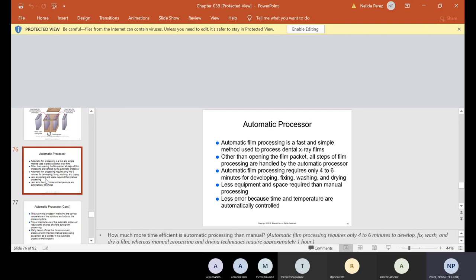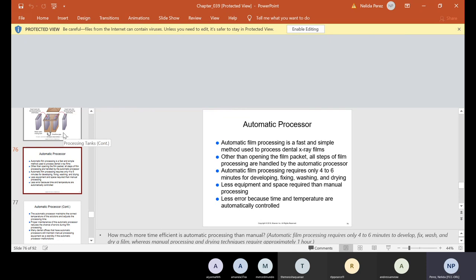The first person who comes in should press start first so the machine can start warming up — all machines need to be warmed up, whether it's the autoclave, ultrasonic, or automatic processor. Think of the lab as your office: you're coming to start everything. Start the ultrasonic, the autoclave, and in this case walk up to the automatic processor first, press start, then go to the autoclave, then the ultrasonic, and go from there. The automatic processor maintains the correct temperature of the solution and adjusts the processing time. Proper maintenance reduces the chance of errors during film processing.